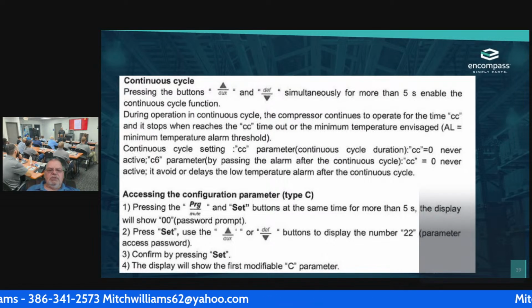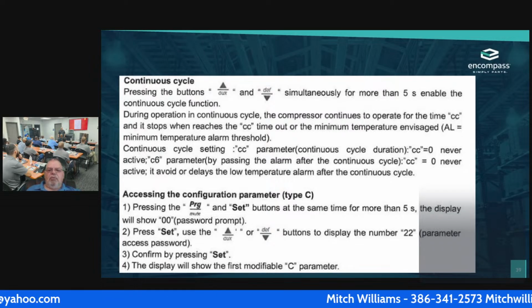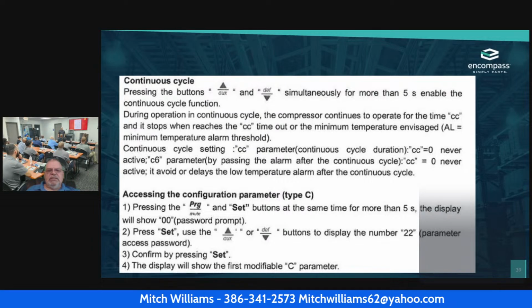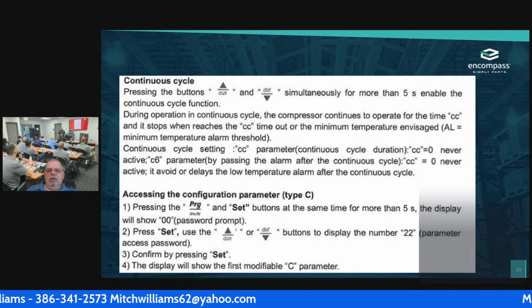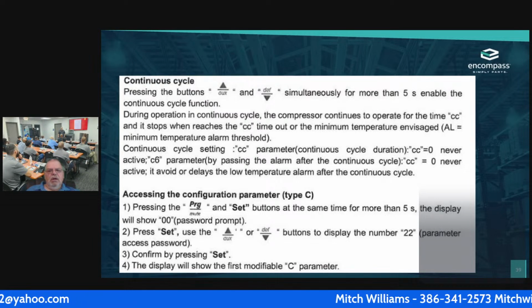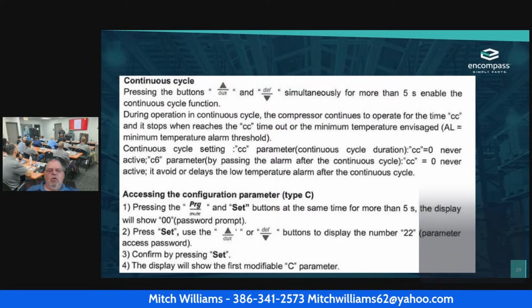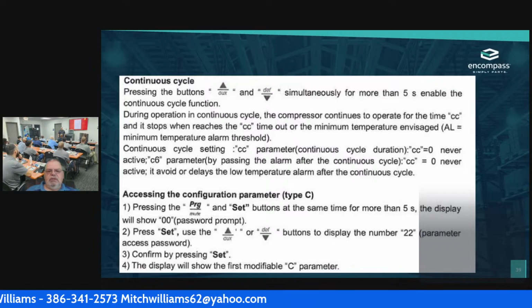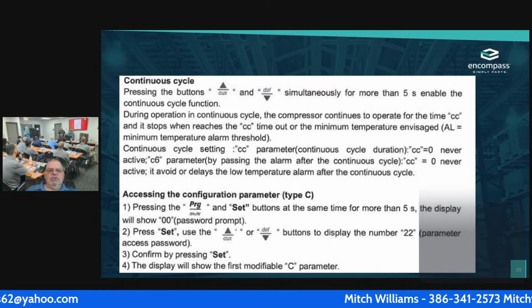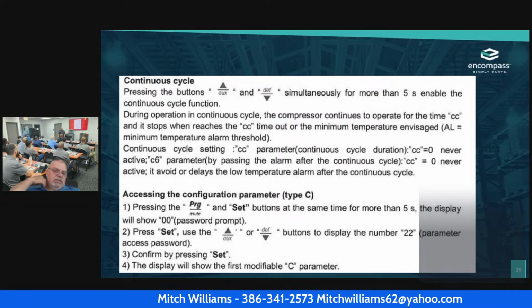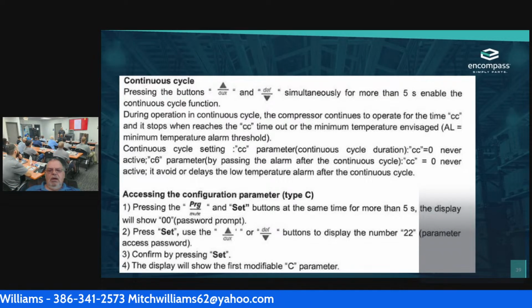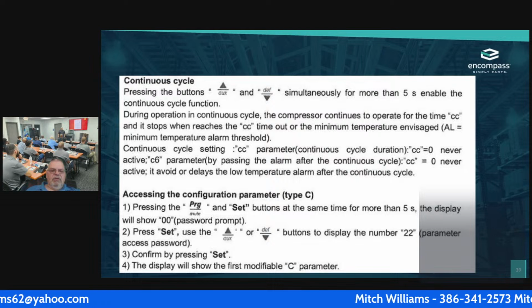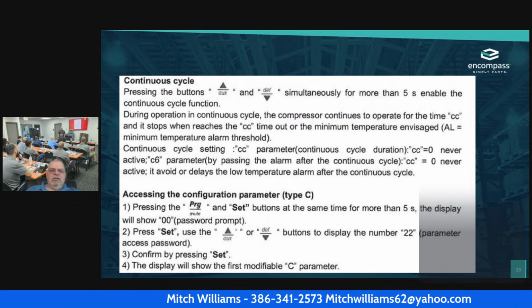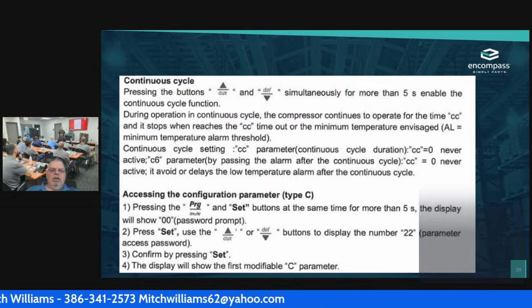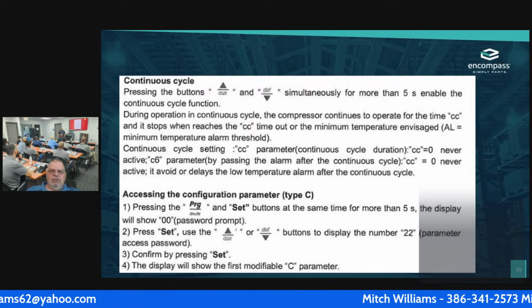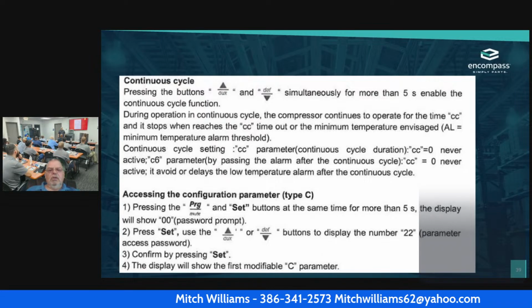During the operation of the continuous cycle, the compressor continues to operate for a time, and then it stops when that CC time is reached. The minimum temperature envisaged is the minimum temperature alarm threshold. Okay, continuous cycle settings: CC in the parameter is the continuous cycle duration. 0 is never active. If I go to the C6 parameter by bypassing the alarm after the continuous cycle, CC is 0, which is never. It also avoids any display of the low temperature alarm after the continuous cycle. So I would definitely want to keep that on.